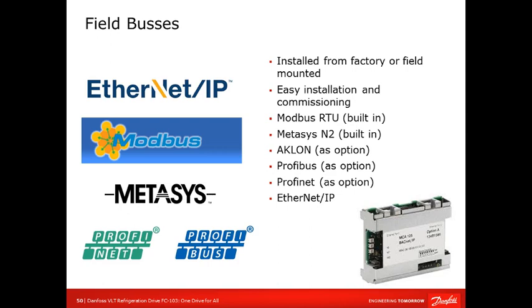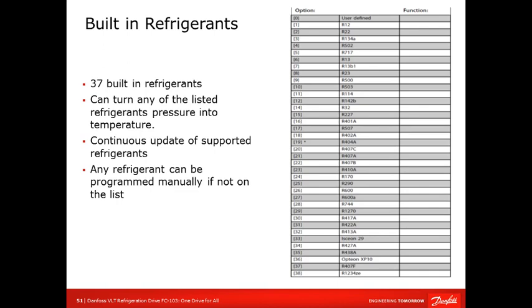And again, some of the field buses. Typically we're asked for Modbus, Profinet, and Profibus, which would be more Europe. But here, obviously, Ethernet IP with Rockwell. For Modbus RTU and Metasys, that's built in. Then we have other options. Again, this is an example there. That card is a BACnet card. It's just an option card that fits right behind the local control panel, so it's something they can add at a later time. And again, easy to work with.